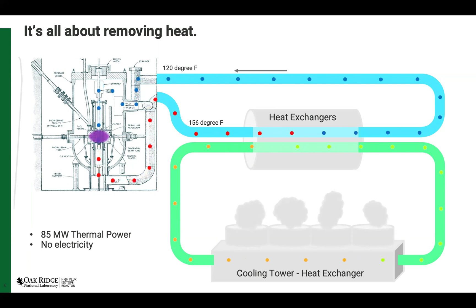The only system that can get activated at all is that primary loop. Honestly, you can calculate the power of 85 megawatts if you know that this reactor flows about 16,000 gallons per minute and heats up with a delta T of 36 degrees.